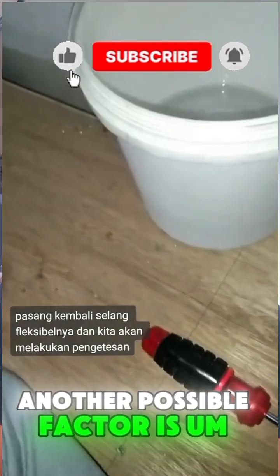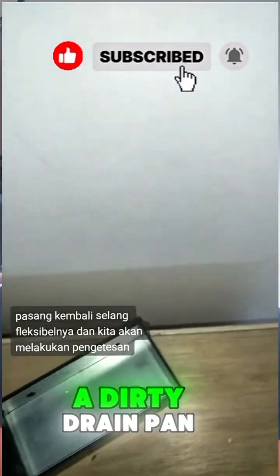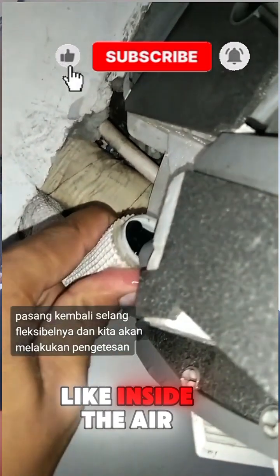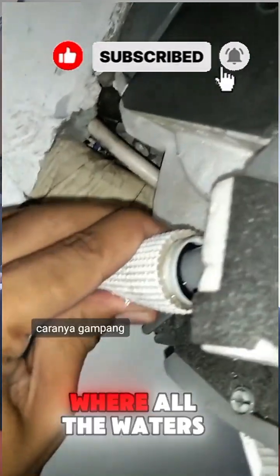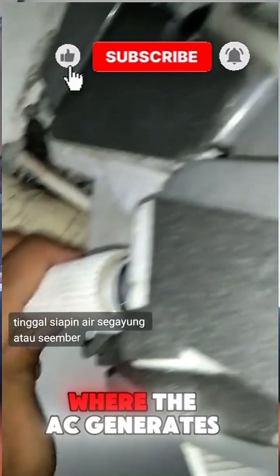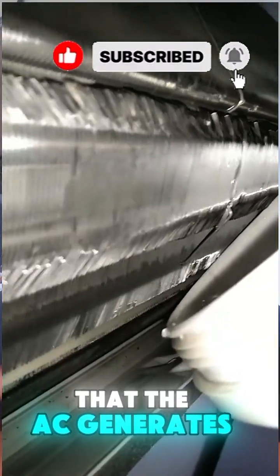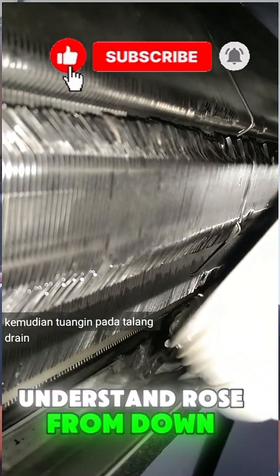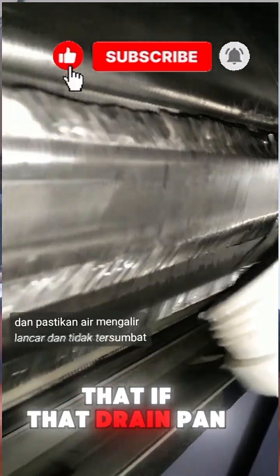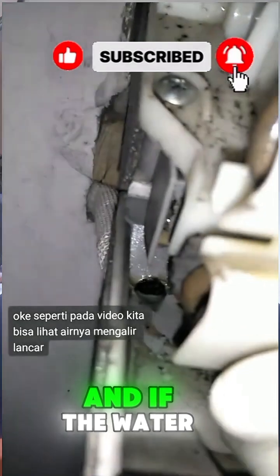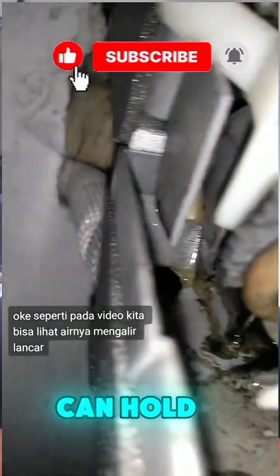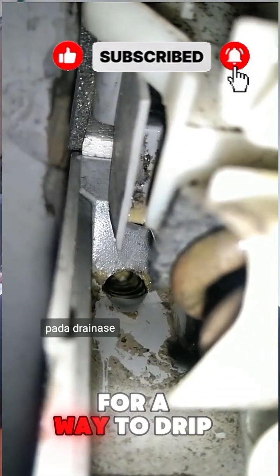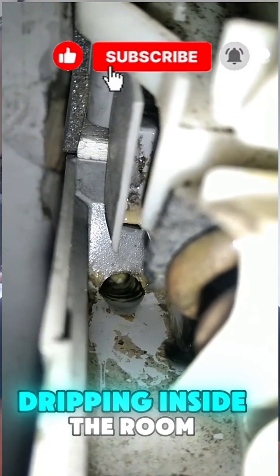Another possible factor is a dirty drain pan. Inside the air condition system, there is a pan where all the water that the AC generates rolls down to the drainage pipe. If that drain pan is dirty, it will accumulate water, a large quantity of water. And if the water accumulates beyond what the AC can hold, it will always look for a way to drip. So that is when it will start dripping inside the room.